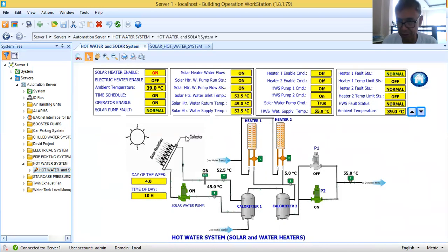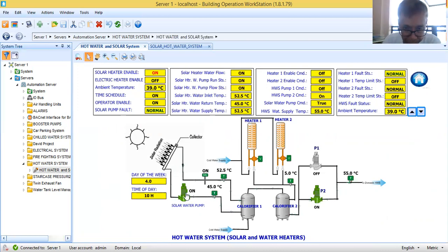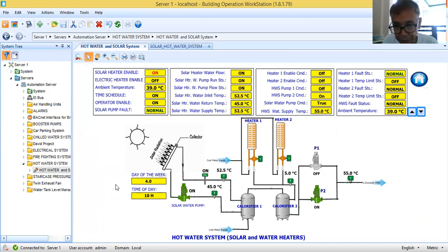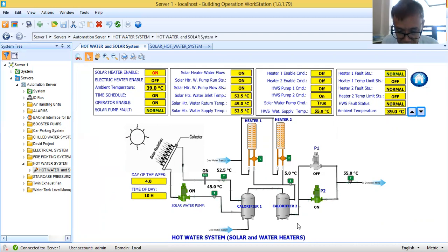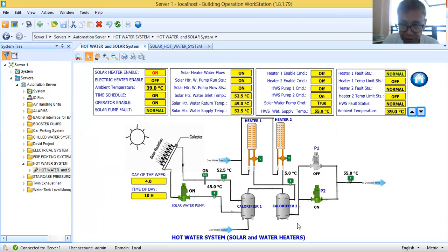Once it is within the daytime hours from six to five, the solar pump will automatically be enabled and start. For the electric heater, it will start when it is past five in the afternoon up to 5:59 in the morning. This is how I wrote the control logic program for this hot water system with solar and electric water heaters.